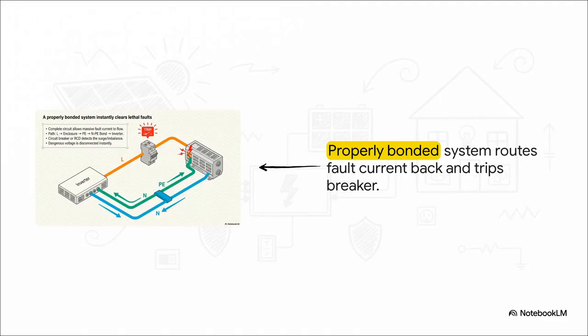Now compare that to a properly bonded system. When that same fault occurs, the current flows into the enclosure, but this time it travels rapidly down that solid green PE wire, crosses that crucial NPE bond we just built, and safely completes the circuit right back to the inverter. Boom. A massive surge of current flows, and it instantly trips the switch, cutting the power and removing the danger in mere milliseconds. That bond is literally a lifesaver.